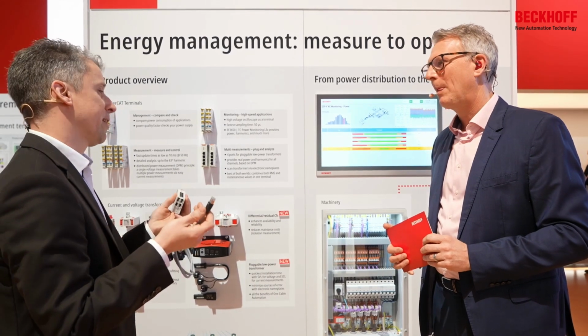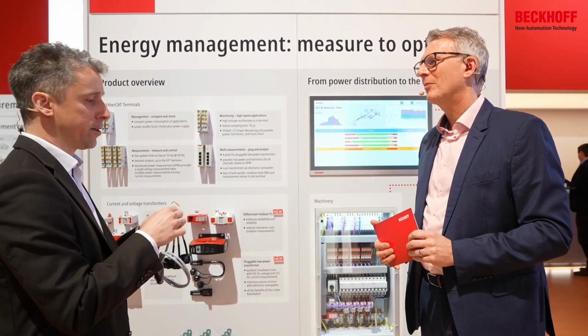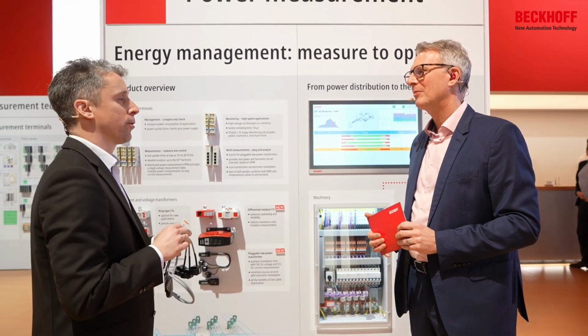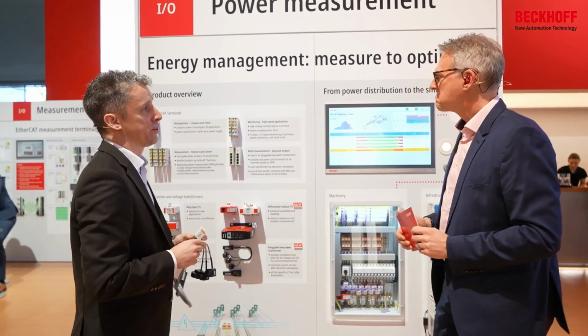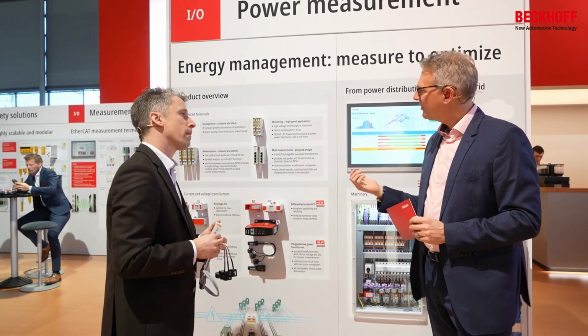Because the current needs to flow. If the primary current is flowing, then the secondary current also needs to flow, and if that's not possible, the transformer can be damaged. Here, as I said, we're using 333 millivolt, so now we have a voltage interface. That makes the system way easier, because you can get rid of the shorting terminals which usually need to be in between.